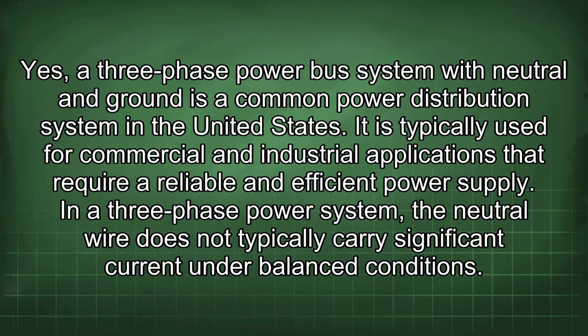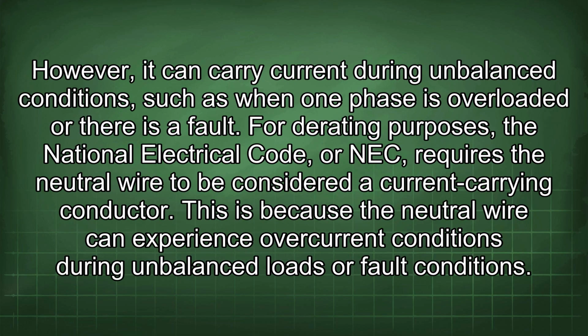Yes, a three-phase power bus system with neutral and ground is a common power distribution system in the United States. It is typically used for commercial and industrial applications that require a reliable and efficient power supply. In a three-phase power system, the neutral wire does not typically carry significant current under balanced conditions. However, it can carry current during unbalanced conditions, such as when one phase is overloaded or there is a fault.